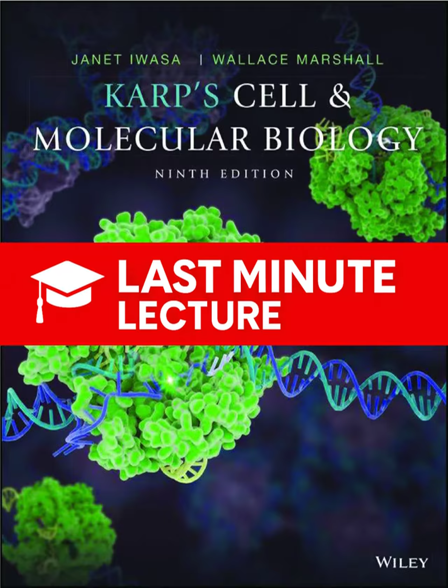Theoretically, yes. But practically, the magnetic lenses in a TEM have severe spherical aberration, so that forces us to use a very small numerical aperture, which brings the practical resolution for looking at a cell down to about 10 to 15 angstroms. Still, vastly better than light. And the machine itself is this huge, tall column, a vacuum column, because air molecules would scatter the electrons.